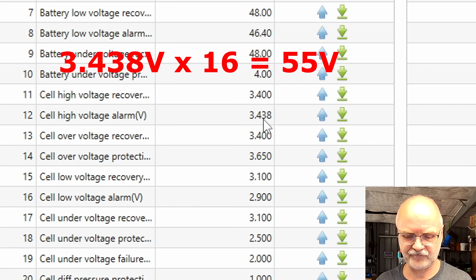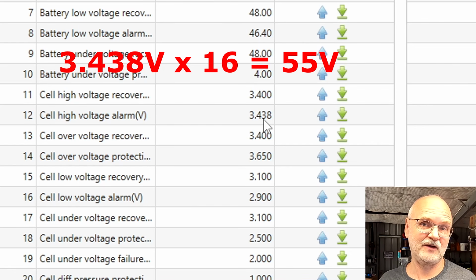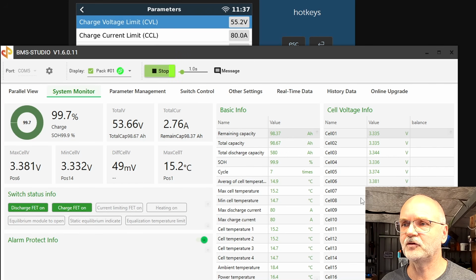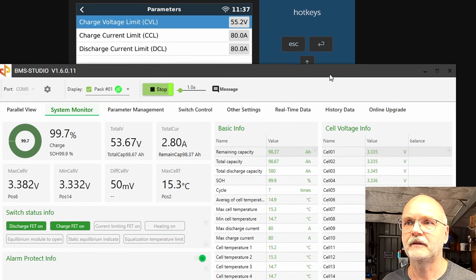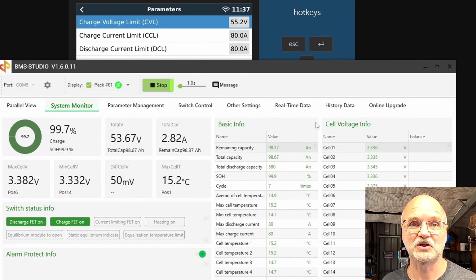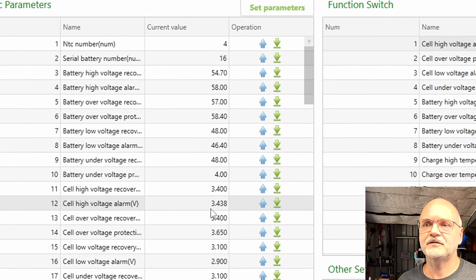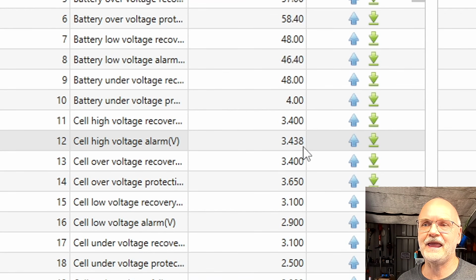So this is like 3.438 times 16. This would be exactly 55 volts. So the battery voltage needs to be over 55 volts for half an hour, and then it resets to 100%. Okay, let's give this a few minutes here until the first cell hits the high voltage alarm again. It may take a moment. Okay, so at 3.438, we have a cell high voltage alarm, right? With one of the cells.